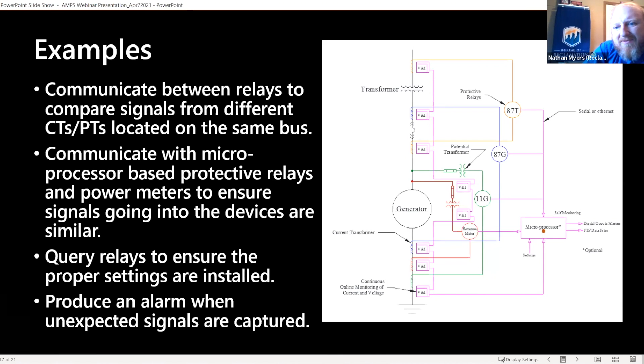So if we look at this drawing here, we're going to look at the 11G relay, which would be a microprocessor-based relay, and we're going to look at the revenue meter. We'll have currents and voltages going into those devices. From there, we would like to query the relay back to a device that can then compare the current and voltage values seen by both the protective relay and the revenue meter, to ensure that they're within the appropriate values and not outside of calibration. Additionally, we would like to look at the overall burden if possible. That would be an optional task. And if we could look at that additional burden, we'd like to record that with the same box as well.